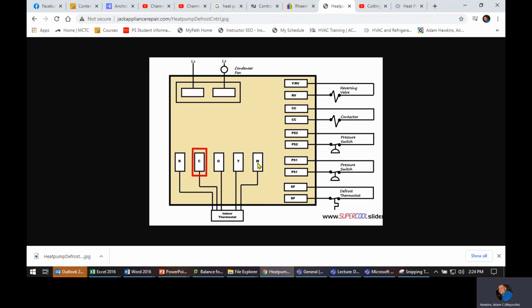So what you're going to do is you're going to also, that board is going to bring in W. Now, what is W? W is your auxiliary heat, your backup heat. In most cases, it's electric heat strips, but not always. But whatever your backup heat source is, that W is going to bring it in. So that is your second stage. So in a heat pump, Y is your first stage, W is your second stage.